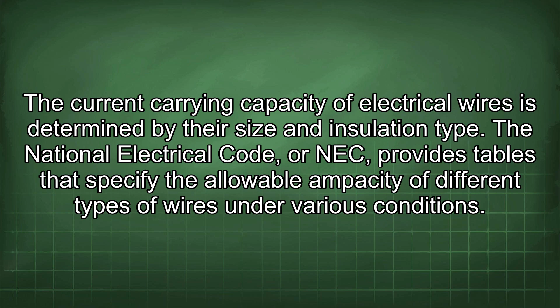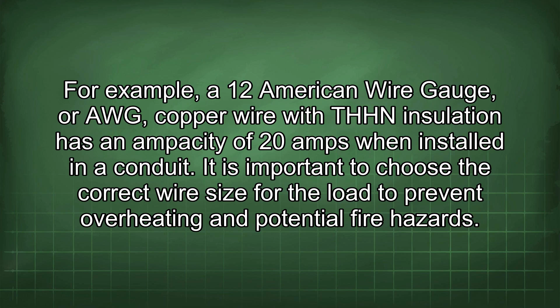The National Electrical Code, or NEC, provides tables that specify the allowable ampacity of different types of wires under various conditions. For example, a 12 American wire gauge, or AWG, copper wire with THHN insulation has an ampacity of 20 amps when installed in a conduit. It is important to choose the correct wire size for the load to prevent overheating and potential fire hazards.